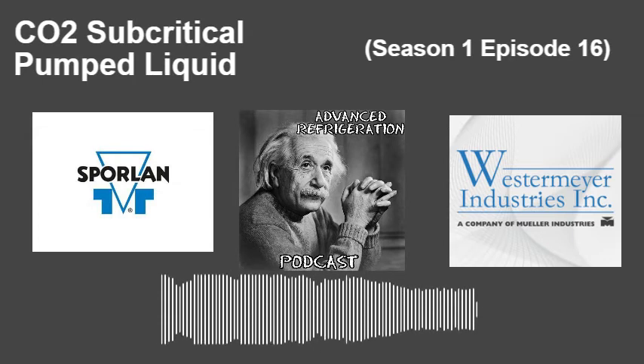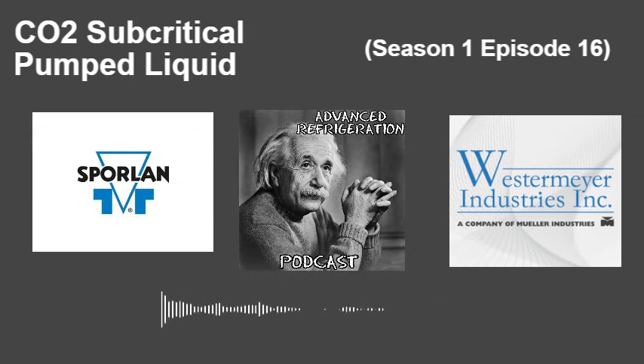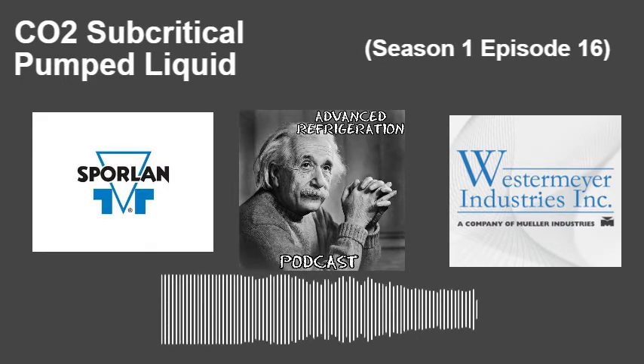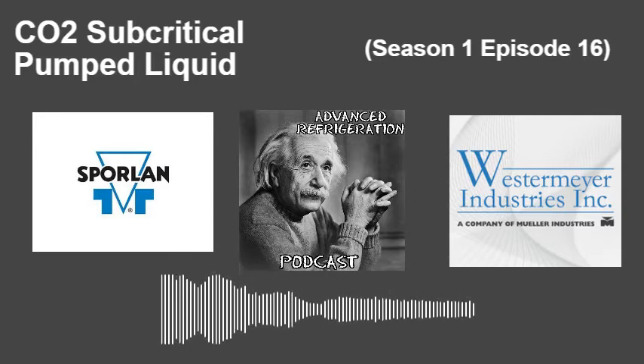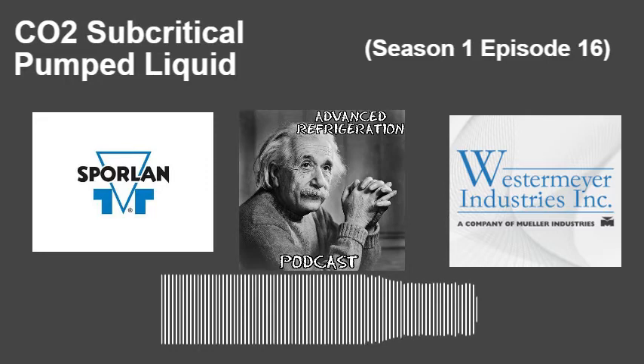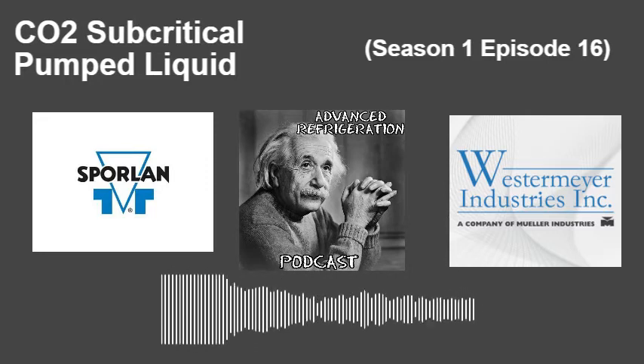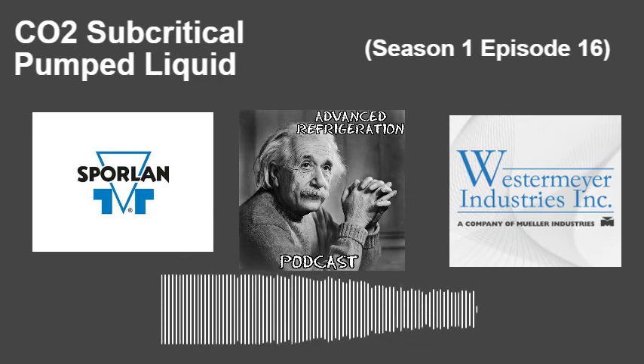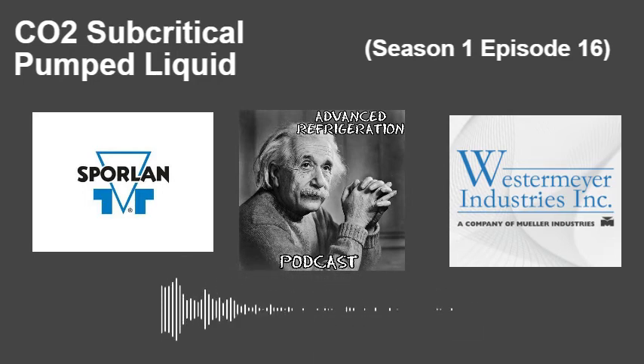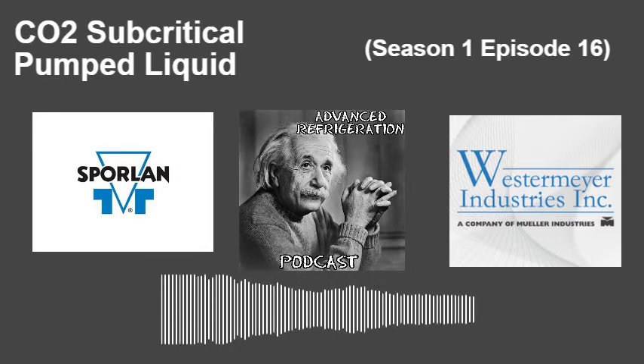If you're isolating the case, every case has its own ball valves. So that is the easiest way to isolate it. If you're going to service it, make sure you take the coil off and use a magnetic plunger, so that you can change a solenoid or something. These solenoids are special CO2 solenoids most of the time. They're XPS valves. They're designed for the fluid flow for CO2. So just make sure you're not putting an ME6 or an ME9 in there. Make sure you're actually using one of these XPS valves. They're designed to close at a lower differential pressure across them, and they have a beefed up spring inside of them to hold them back.